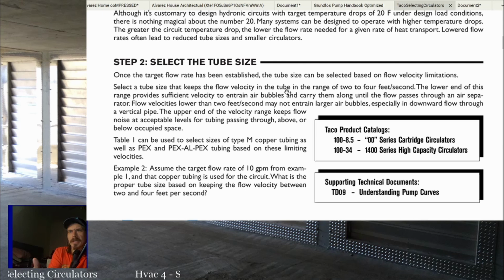But in this case, we're going to talk about it as if we're selecting it from the beginning. So once the target flow rate has been established, the tube size can be selected based on flow velocity limitations. Select a tube size that keeps the flow velocity in the tube in the range of 2 to 4 feet per second.